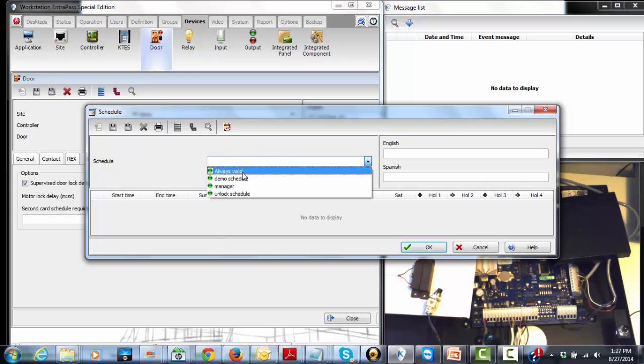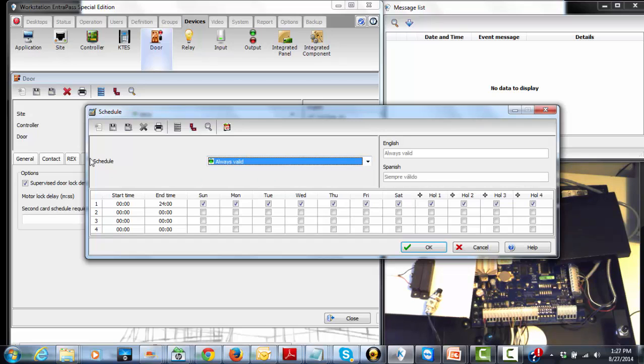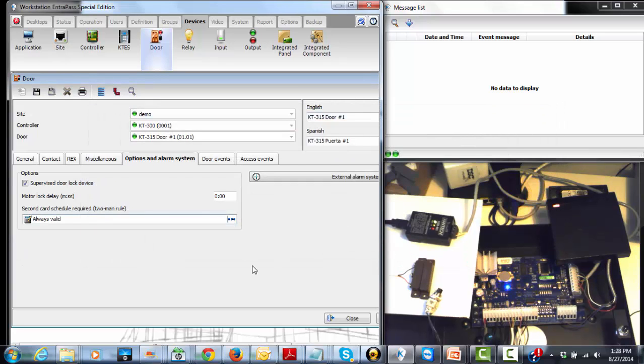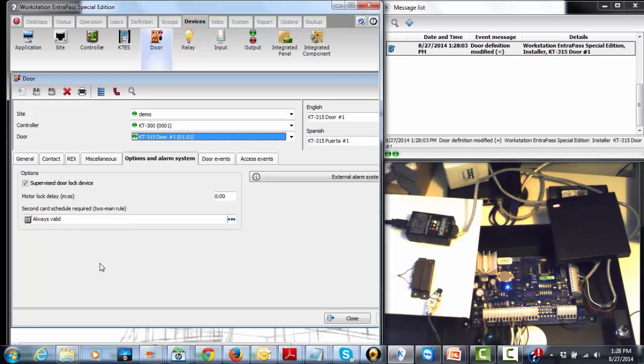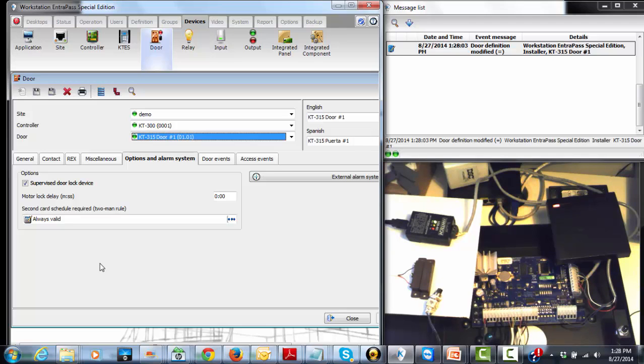We can create a schedule. For this one, we just go with always valid for my testing. But in your case, depending on the system, some customers require two-man rule after business hours. For example, during business hours, one authorized user can access the door, but after business hours they need two users depending on how they want it. So you're just going to create the schedule for that.